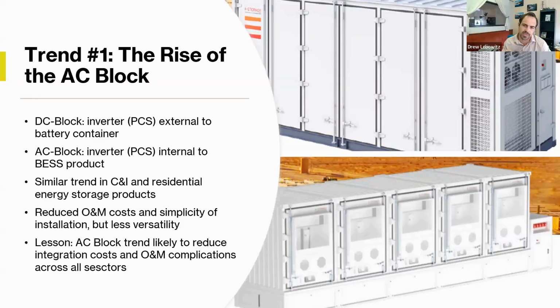As opposed to most of the time with a DC block, you only get the performance guarantee... and when I say performance guarantee, it's energy and round trip efficiency for usually the life of the system, 20 and sometimes 25 years. So technically there's no huge difference in terms of the round trip efficiency you'll get AC block versus DC block. But contractually speaking, and how complicated it is, there's a simplicity of having the round trip efficiency for an AC block product at the AC terminals as opposed to the DC terminals.